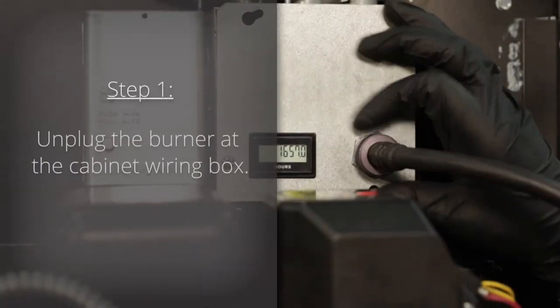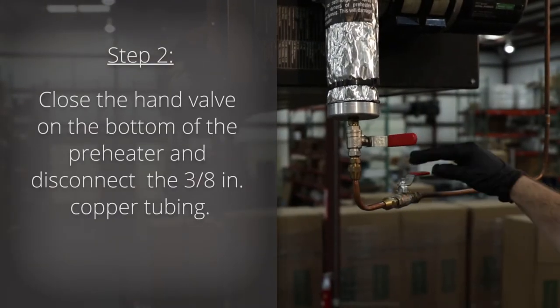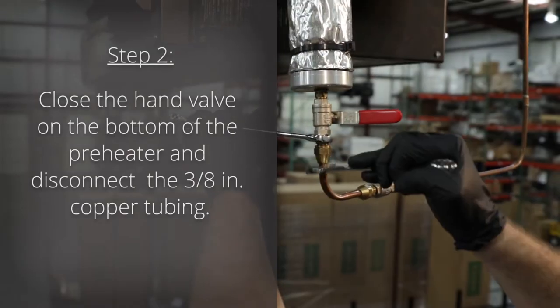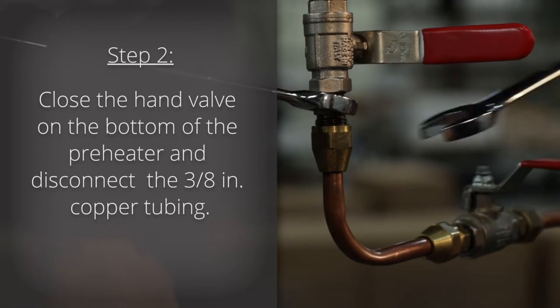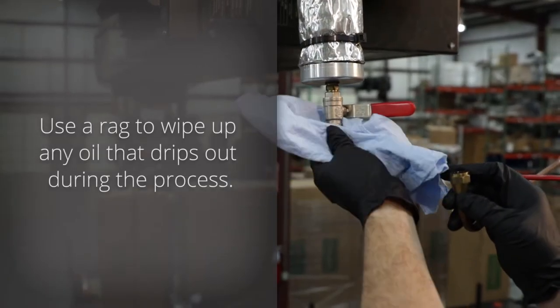Step one, unplug the burner at the cabinet wiring box. Step two, close the hand valve on the bottom of the preheater and disconnect the 3/8 inch copper tubing. Use a rag to wipe up any oil that drips out during the process.